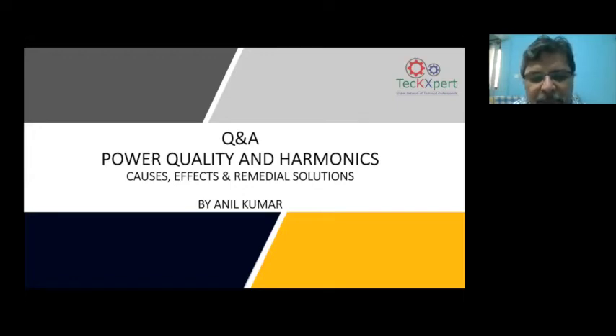And are there any government rules for harmonics, like PF that has to be maintained by the end user? Do you have any proposal, or are there any such rules in our Indian government? The power factor regulation, according to the Central Electricity CEA Act, true. CEA has come out with the regulation saying that the PF should be plus minus 0.95. That means you can go to leading also 0.95, but lagging should not be below 0.95. But then the utilities, state electricity boards have their own ways, so that is where the problem is. Now in Maharashtra, it is very particular, the reactive energy, leading and lagging are all penalized. Karnataka, I don't think any penalty is there.